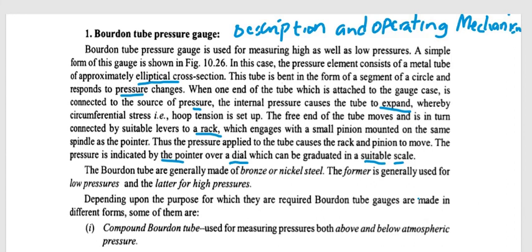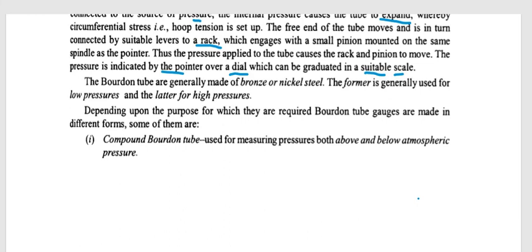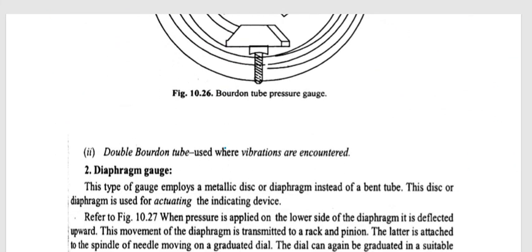Bronze is generally used for low pressures and nickel steel for high pressures, depending upon the purpose for which they are used. Bourdon tube gauges are made in different forms; some of them are the compound tube, used for measuring pressures both above and below atmospheric pressure. There is also a double Bourdon tube, which is used where vibrations are encountered.